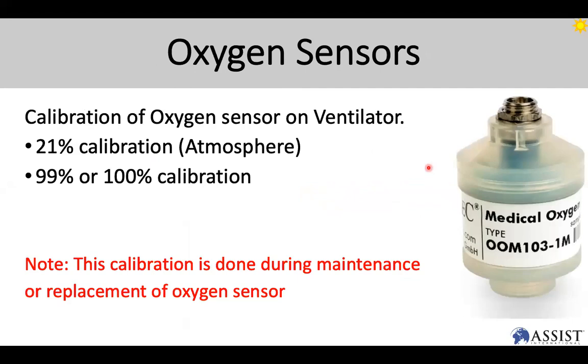As a part of the vent analyzer, a lot of you may have seen this specific component, the oxygen sensor. This is very critical because this is what you will use to calibrate the oxygen sensor on a ventilator. Usually, for those of you who've had the hands-on sessions in our training programs, you know that you'll start with 21% calibration, which is just with atmosphere. And then you will increase the gas, oxygen, and you'll calibrate it at 100%. Now, this calibration is done during maintenance or after the oxygen sensor has been replaced.